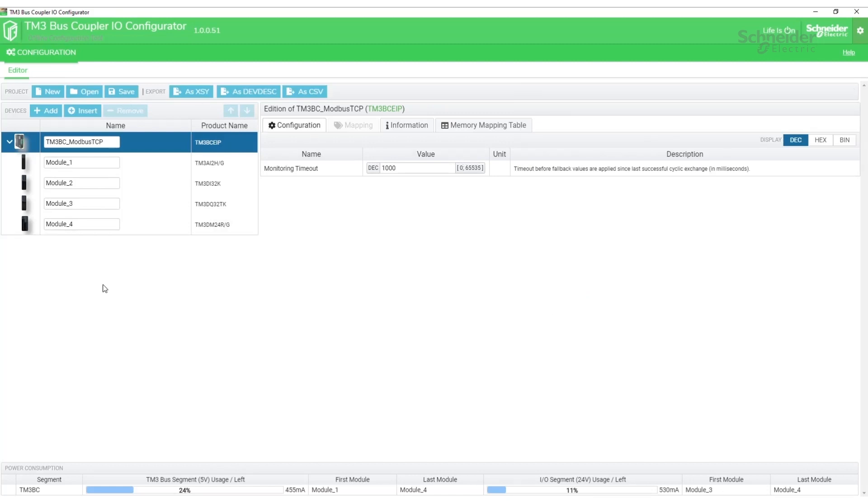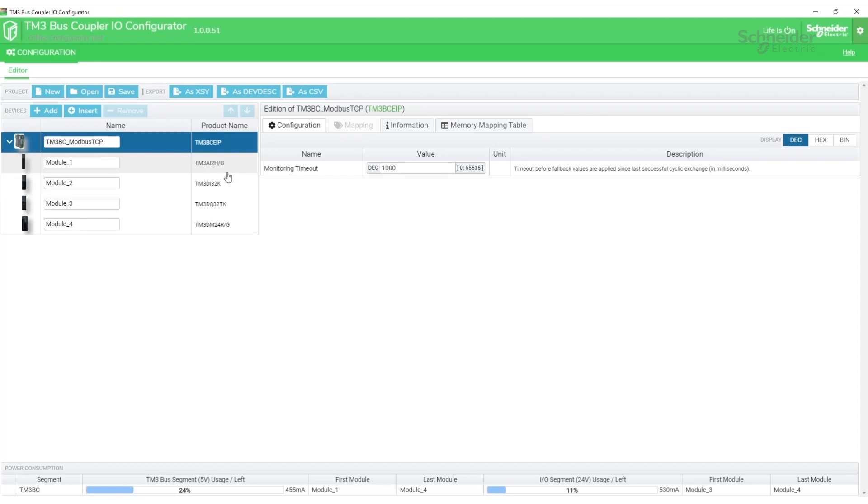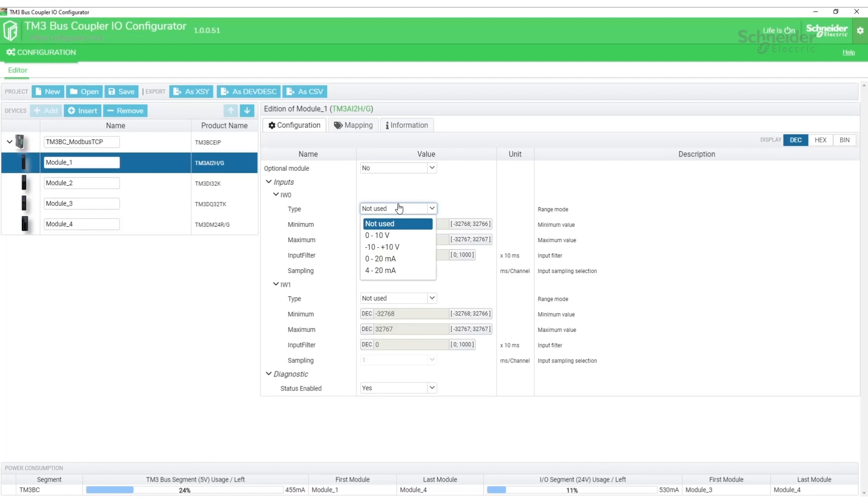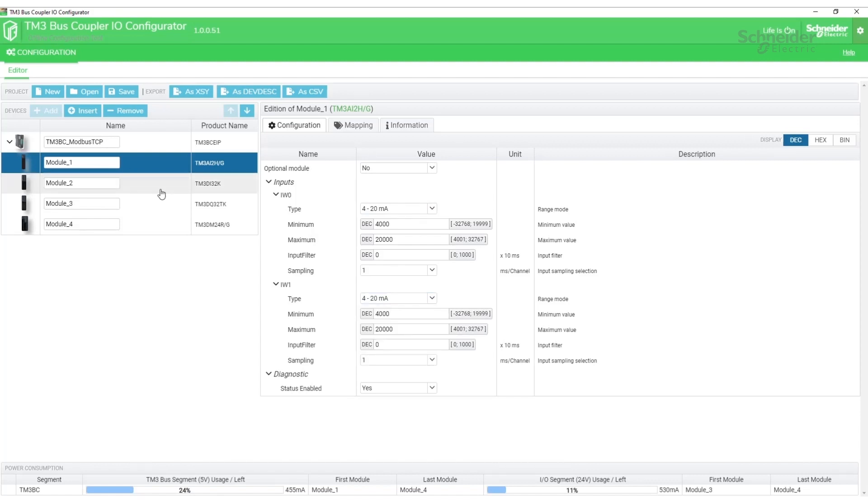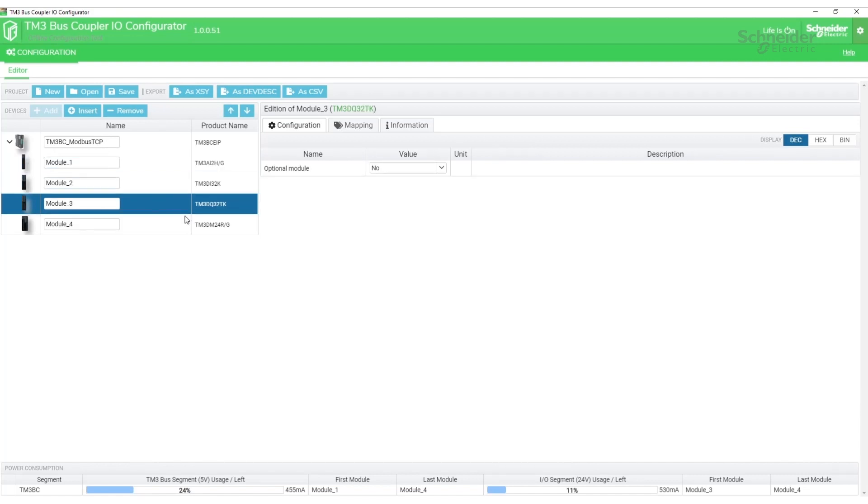Now that I have my modules added to the configurator, I'll want to go into the modules and set up any configuration for the individual module. In this case, I have an analog input module I'm going to want to set it to 4 to 20 on both of the channels. The other modules I'm going to leave at default settings.